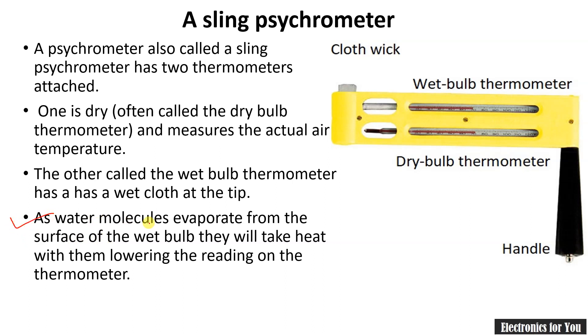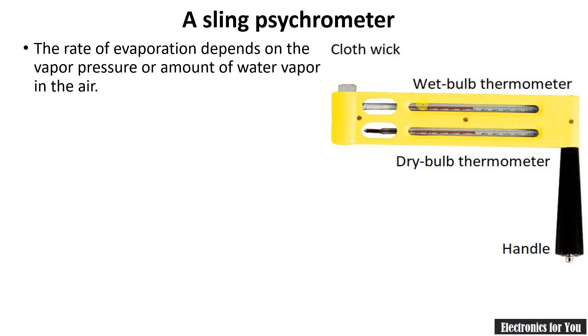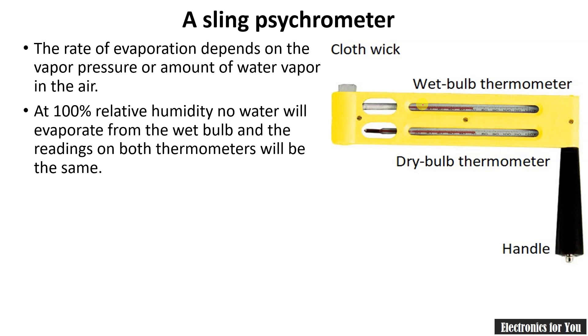As water molecules evaporate from the surface of the wet bulb, they take heat with them, lowering the reading on that thermometer. We wet the wet bulb thermometer, and its temperature starts dropping. The dry bulb thermometer will therefore show a higher temperature compared to the wet bulb. The rate of evaporation depends on the vapor pressure or the amount of water vapor in the air. At 100% relative humidity there will be no difference between the two thermometer readings, but most of the time there will be a difference, with the wet bulb showing a lower temperature than the dry bulb. A specific chart is used for measurement of relative humidity.